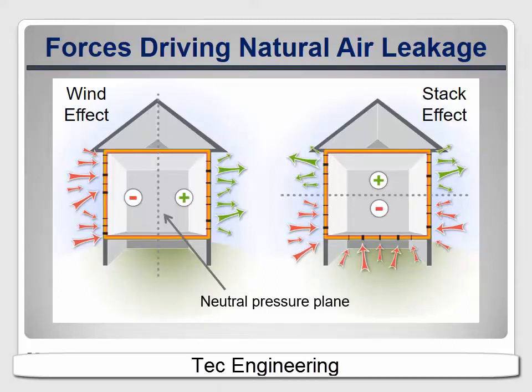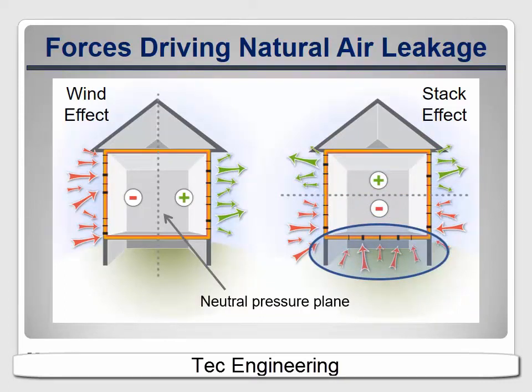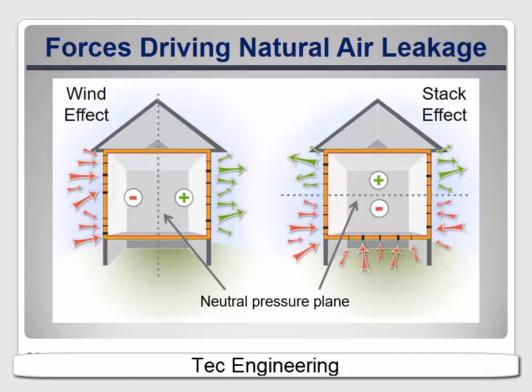The warm air rises and creates a positive pressure at the top and pushes out of any openings. This creates a suction at the bottom of the house that draws cooler air in through openings down low. Again, there's a neutral pressure plane that divides the two, but this time it's horizontal. This stack effect also doesn't happen all the time. It's highest in the winter, when it results in the biggest energy penalty, but it doesn't happen much at all in the warmer months. So there are significant periods through the year when these natural leakage forces don't do much to ventilate the house.